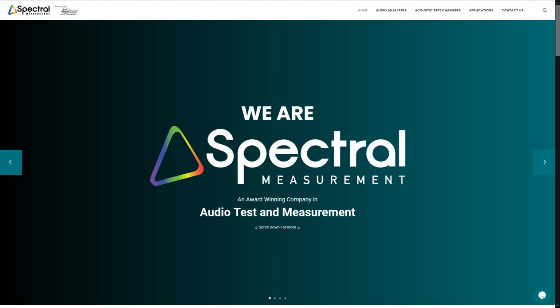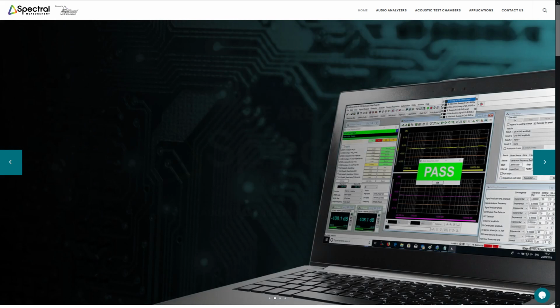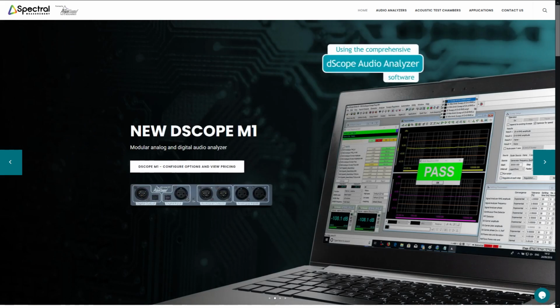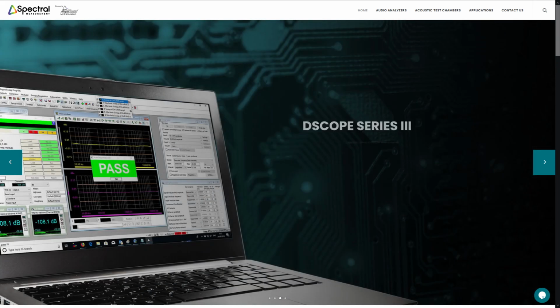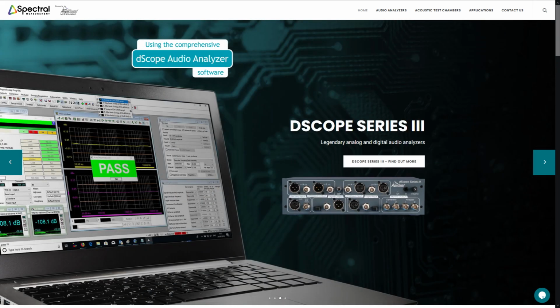Today I'm going to show you how we set up the dScope system to measure a loudspeaker driver, and then how that test can easily be automated for a production QC test using our Autosequence automation tool. This can be done on the bench with the accompanying acoustic limitations, as indeed here, or in an anechoic chamber, or using one of our loudspeaker test chambers to obtain a calibrated equivalent free field response.